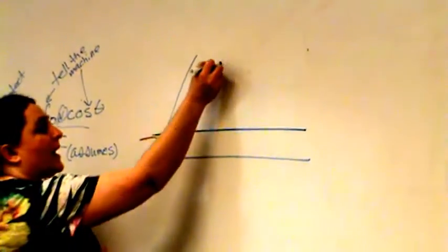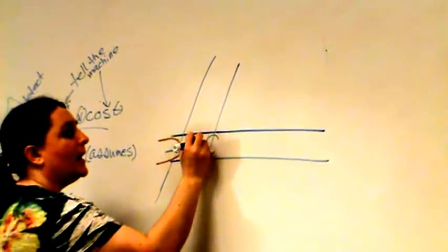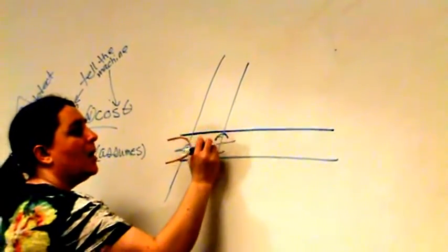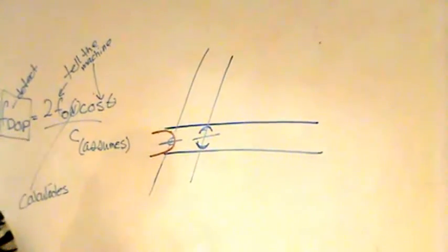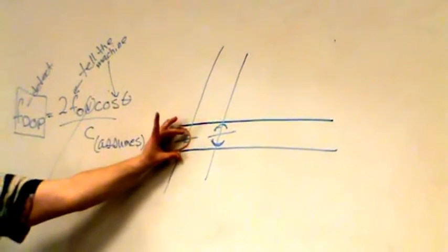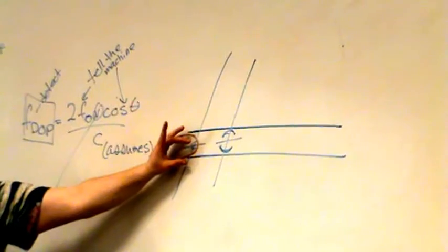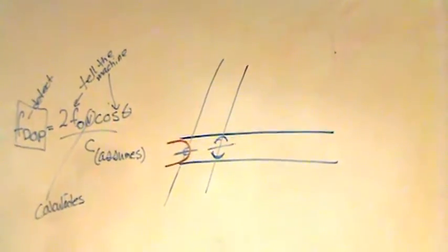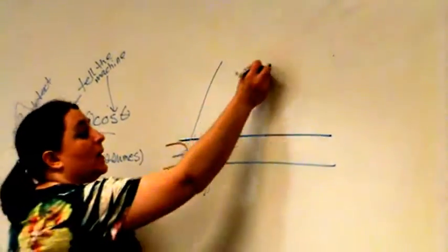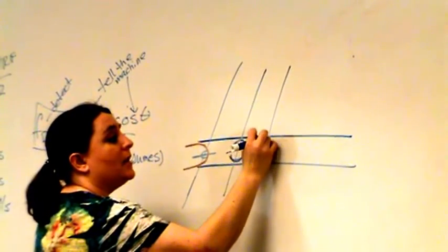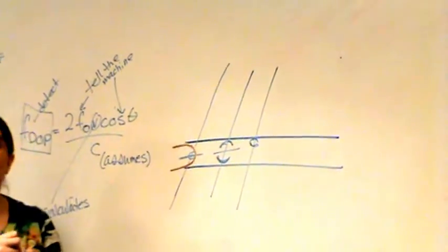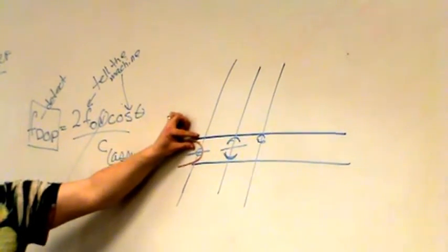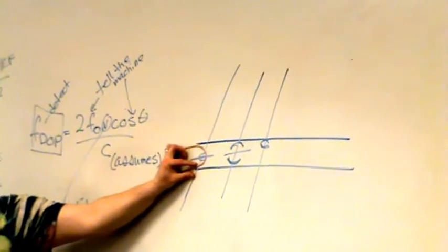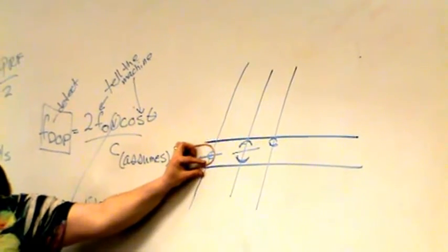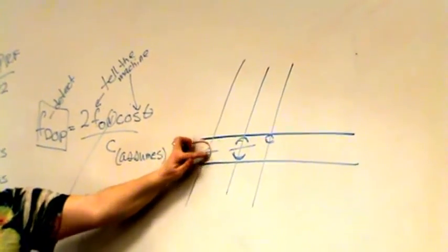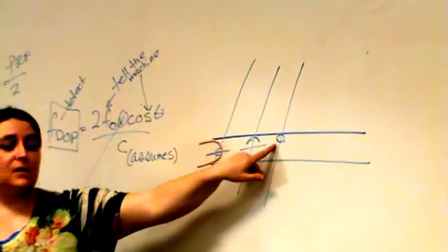If I open my sample volume up wider, maybe I'm still at a good angle, but I open my sample volume up wider, I'm detecting more of this range of velocities in this parabolic flow profile, so that's going to create spectral broadening. If I have a small sample volume up here close to the edge of the wall, on this edge of the parabolic flow, that has more range of velocities than it does in the middle because of the shape of the parabola. So this is going to create spectral broadening.